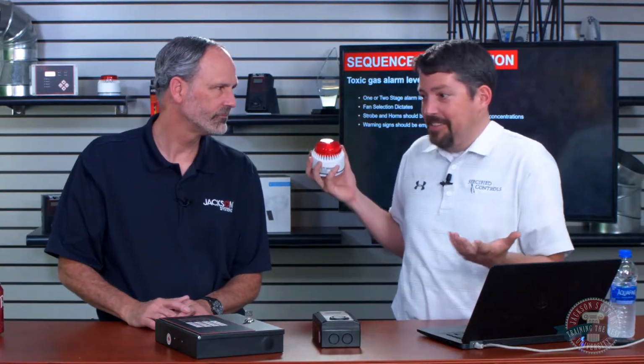And then warning signs, which we'll talk about again in a minute. This is a strobe, as an example, that we would use. If that strobe is above the elevator in a parking garage and it just starts going off and nobody knows what it's about, they think it's the elevator, right? So a warning sign saying what that strobe is for is very important. Rarely is an engineer going to say, yeah, put a warning sign on there. It should be included in your price. Just a plastic sign that says, warning, CO and NO2 levels high, please exit the facility, will help with that process.